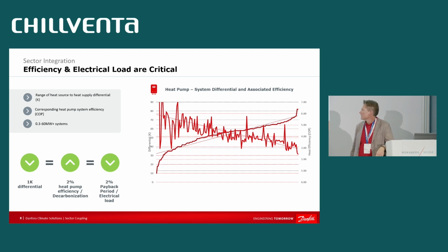This chart, though busy, shows decreasing efficiency with increasing differential, summarized here: for every 1K differential decrease in the work a heat pump has to do, you gain about 2% in efficiency—universal, independent of the technology used—to electrify that heating system. That decreases payback by 2%, but also critically decreases the electrical load. So it's not only about efficiency, it's also about electrical load.